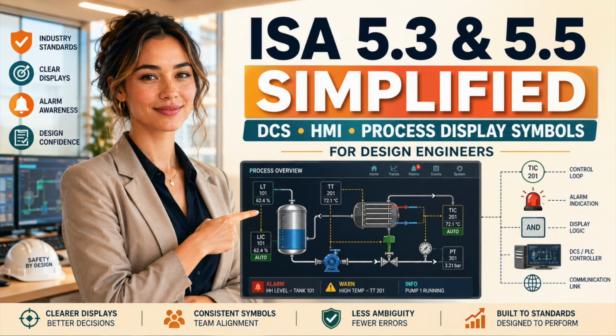During normal operation, experienced operators may compensate through memory. During startup, shutdown, equipment failure, or process upset, the weakness becomes visible. The operator must stop, interpret, and verify before acting while the plant continues to move. Standardization exists to eliminate that unnecessary cognitive load. The process display system should create one coherent language across equipment, process flow, instrumentation, shared control, logic, alarms, and computer functions. It should allow the process engineer, control engineer, operator, and maintenance technician to look at the same symbol and derive the same meaning.